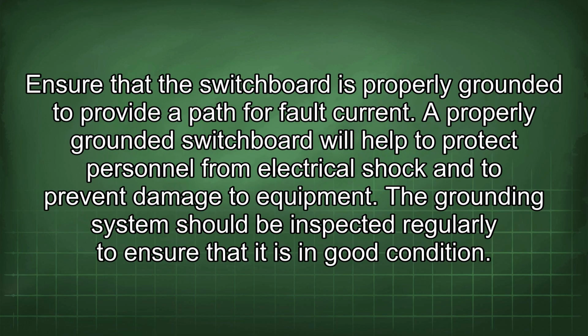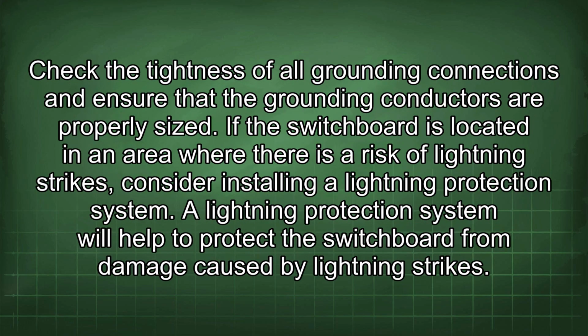Ensure that the switchboard is properly grounded to provide a path for fault current. A properly grounded switchboard will help to protect personnel from electrical shock and to prevent damage to equipment. The grounding system should be inspected regularly to ensure that it is in good condition. Check the tightness of all grounding connections and ensure that the grounding conductors are properly sized.